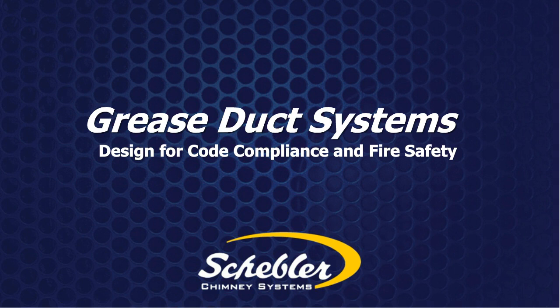System size is going to really depend, by configuration, on what the cost savings would be. Honestly, I can tell you, I think we compete head-to-head with field fabricated product. In some cases, almost a no-cost increase if we're really having the contractor factor his cost all in. So his time to fabricate in the shop, his time to field weld, his time to go through inspection, his true cost of supports for that system, and recognizing his true installation cost at the beginning of the project. A lot of times the project's bid originally is built all field fabricated with a whole installation package, and then sometimes we get compared on the backside and only a small part of installation gets split out. So I really like to think that we're almost at a wash if all costs are factored in.